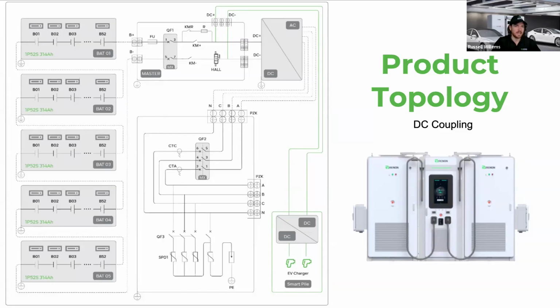There are a couple of approaches to topology for integrating this battery and EStand system. The standard approach is our DC coupled system, where each battery has its own PCS, allowing it to be AC coupled to the grid. The grid can flow directly into the batteries, which slowly charge and provide additional storage, and while charging we can direct DC power straight to those chargers.